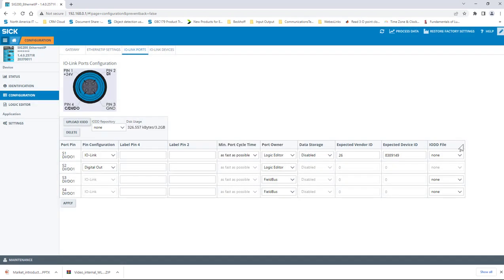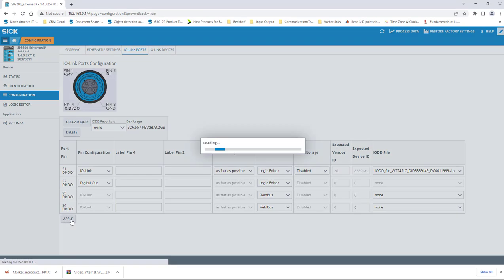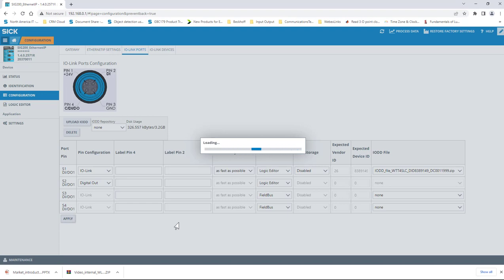Click the IO-DD file drop-down associated with port S1 in the top row of the table. Assign the WTT4 IO-DD file just uploaded to the port by clicking on the file name and then click Apply to save it to memory. A word of caution here, be patient while the SICK stores the file into memory. Sometimes this can take up to 15 seconds or so.